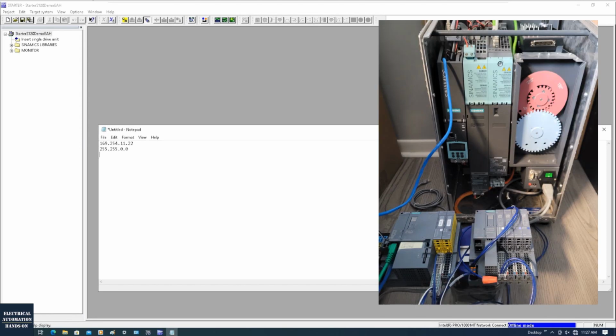Since I'm connecting to the front port of the S120 CU control unit, this port is basically used for commissioning and configuration. By default, this port's IP address is 169.254.11.22, and its subnet is 255.255.0.0. Basically, the IP address of this port won't be changed because the port is only used for configuration and commissioning. It will not be used for communication between the PLC and the S120. According to this IP address, we need to set the IP address of our laptop in the same subnet.